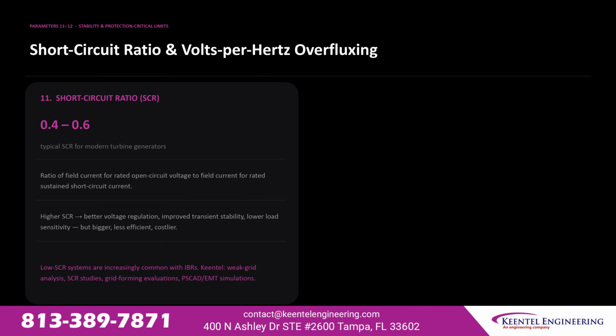Short circuit ratio for modern turbine generators typically runs 0.4 to 0.6, the ratio of field current for rated open circuit voltage to field current for rated sustained short circuit current. Higher SCR means better voltage regulation and improved transient stability, but a bigger, less efficient, costlier machine. Low SCR systems are increasingly common with inverter-based resources, requiring weak grid analysis and PSCAD EMT simulations.